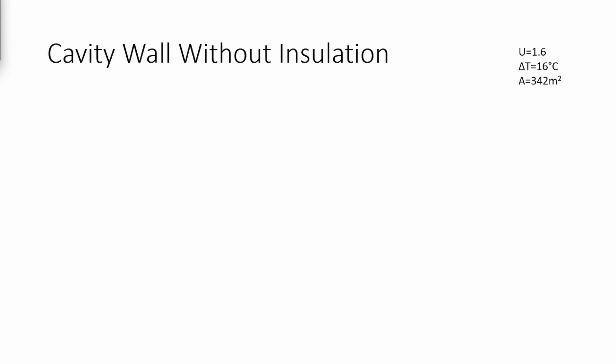We start off with cavity wall without insulation, which is what we currently have. The U-value of this is 1.6. We're going to assume for each case that the temperature inside the house will be 21 degrees, while the temperature outside is 5 degrees. Gotta love classic British weather. Now using the heat loss equation, we can find that the total heat loss is a whopping 8,755.2 watts.